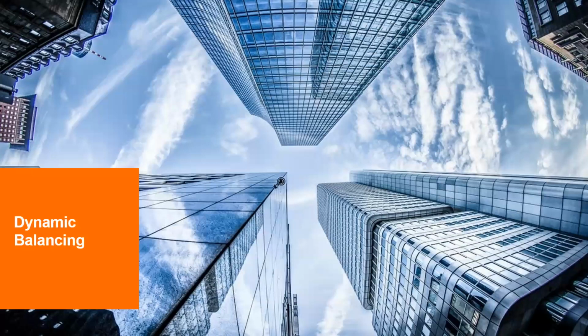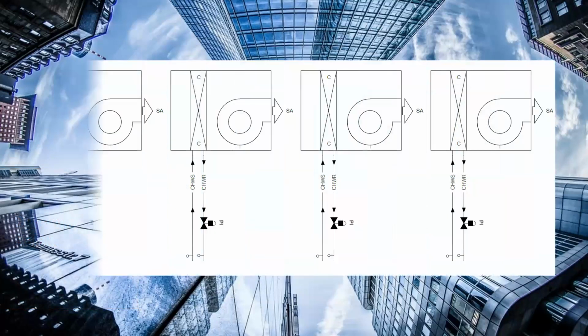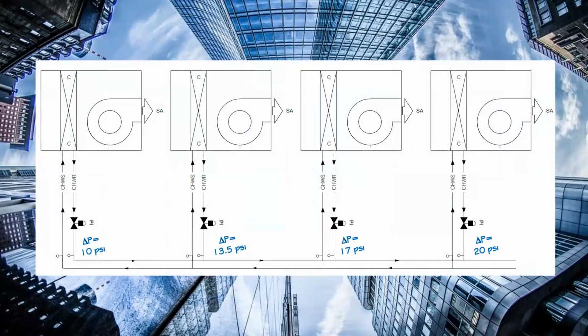Pressure-dependent systems are statically balanced. Pressure-independent systems are dynamically balanced. They're always balancing themselves. As you know, we showed our fan coils, and we have different pressure drops or branch pressures that increase as we move closer to the pumping source. But what you'll notice here is there are no balance devices. This would be a pressure-independent system where that pressure-independent valve is essentially giving exactly what that coil needs at all times and continually balancing with increases and decreases in pressures.